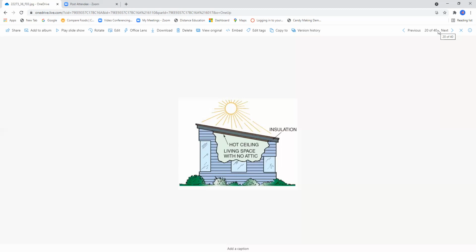I would strongly urge you to look at purchasing or investing in a structure that has an attic where you can separate the ceiling area from the roof line. Otherwise, you're going to have a hot house in the summertime. You will be running air conditioning practically nonstop. I noticed that you see this type of construction out in Indio as well as Palm Springs in older houses. I personally do not like it, and I have told people that I am not going to bid on projects utilizing this type of construction because the cooling load is very excessive.